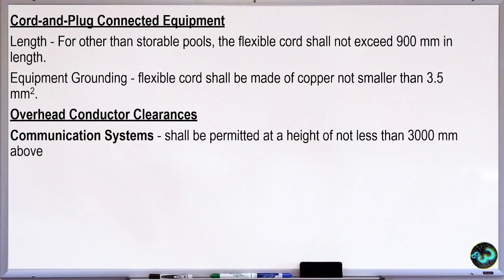Cord and plug connected equipment. For cord and plug connected equipment, the length, for other than storable pools, the flexible cord shall not exceed 900 mm in length. The equipment grounding flexible cord shall be made of copper, not smaller than 3.5 square mm. Overhead conductor clearances for communication systems: the communication system wires, like Wi-Fi cables, shall be permitted at a height of not less than 3,000 mm above the surface of our pool.